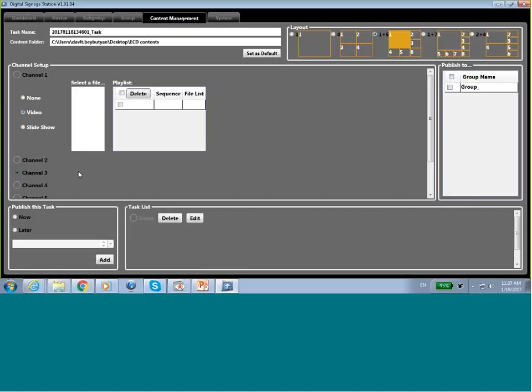So in this case, I need to connect this PC with the ECD1000, or can I do it remotely? We can do it remotely as well. Okay, so do we do port forwarding as well for the ECD1000? If we're in the same network, it won't be a problem. We don't need to do port forwarding. We will need port forwarding when we're accessing the device from outside of the network. But it's just a one-time setup, and you can remove the PC. So it's just a one-time tool.